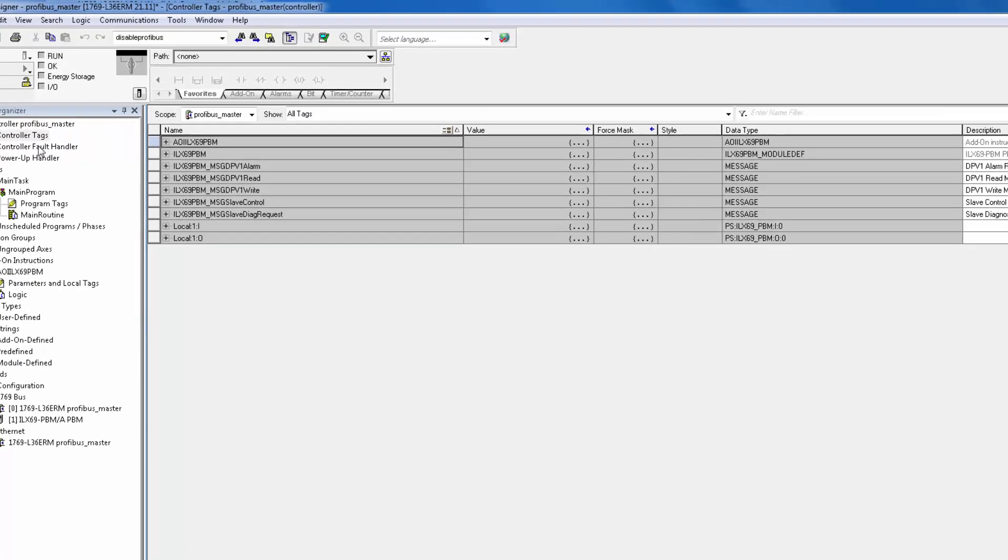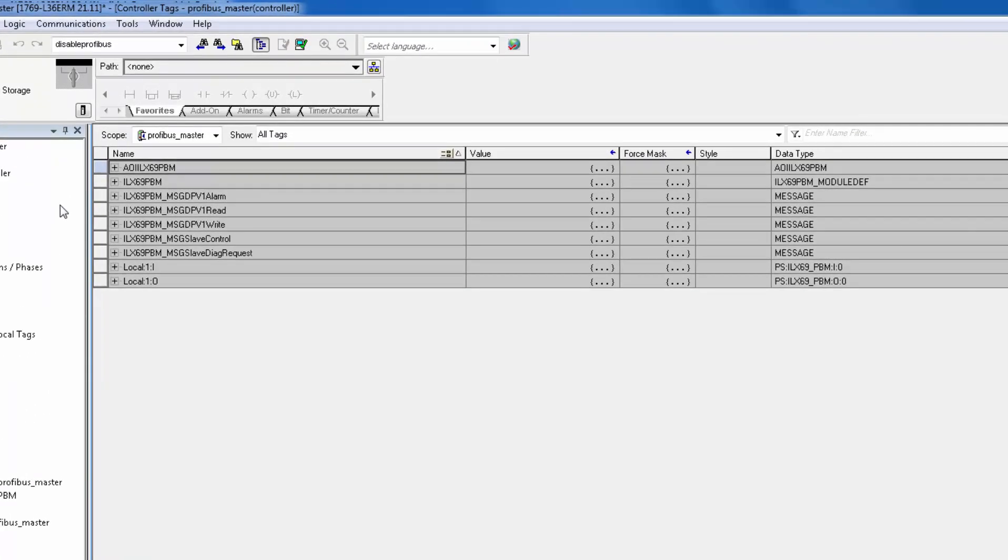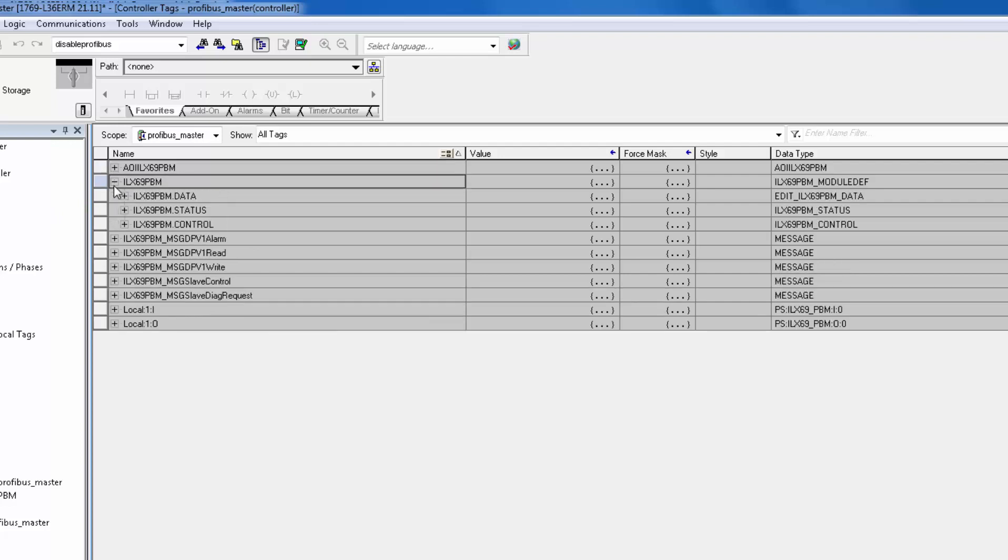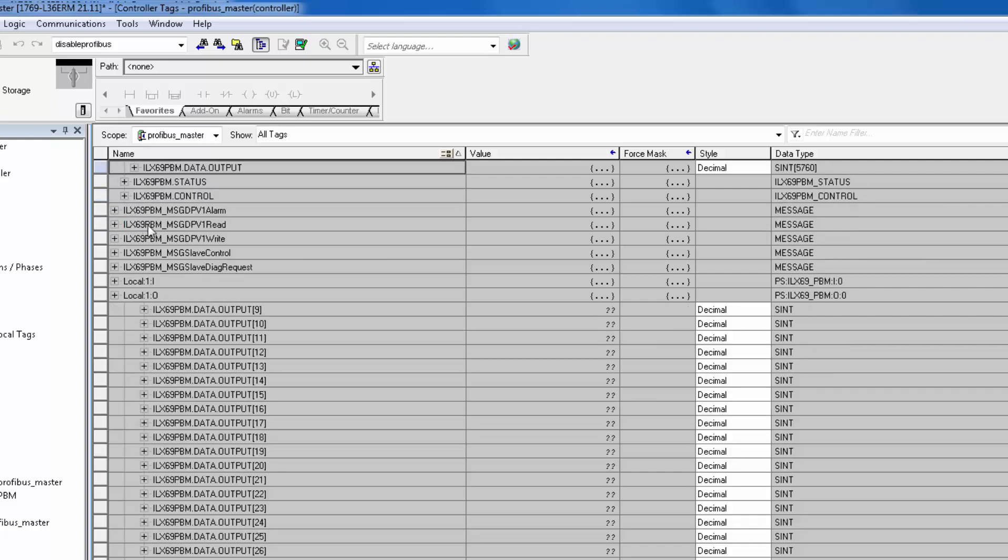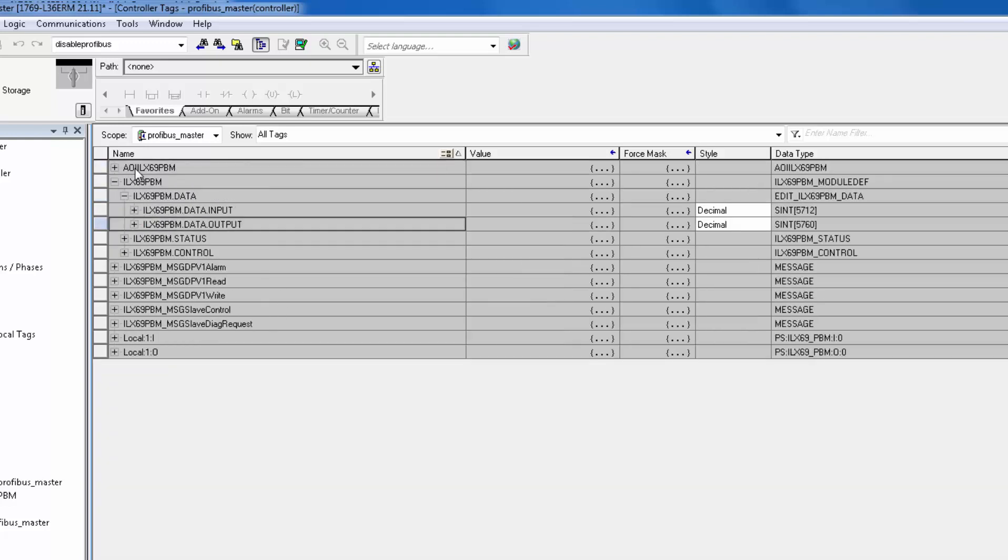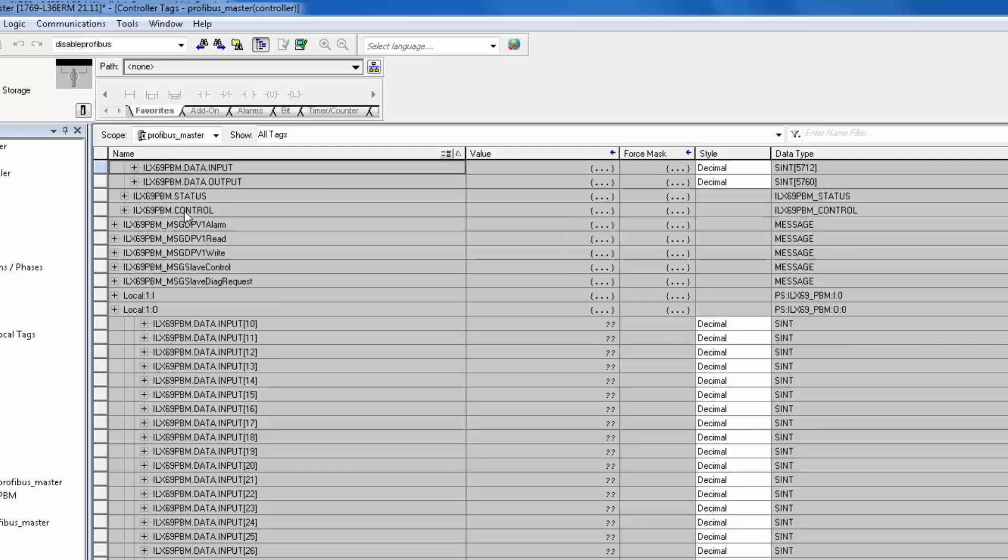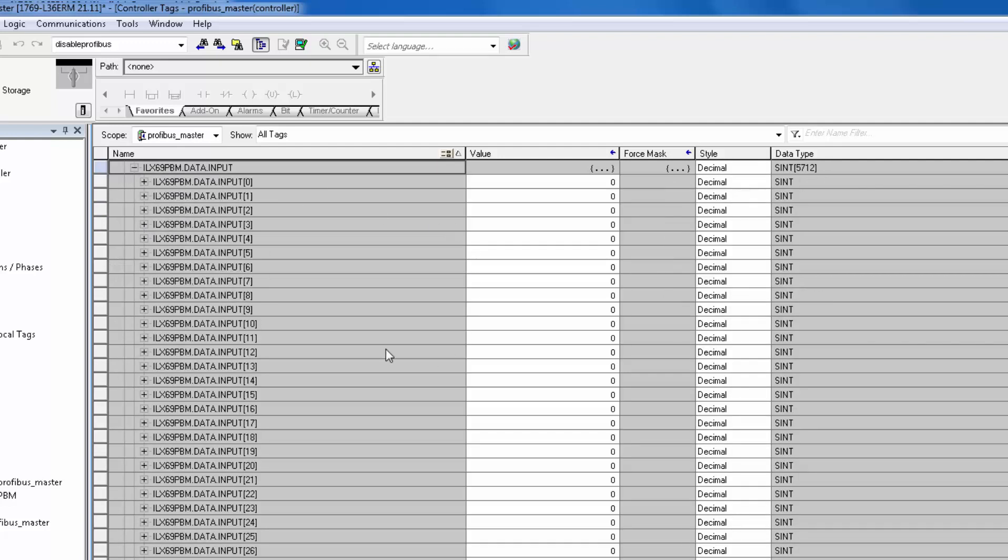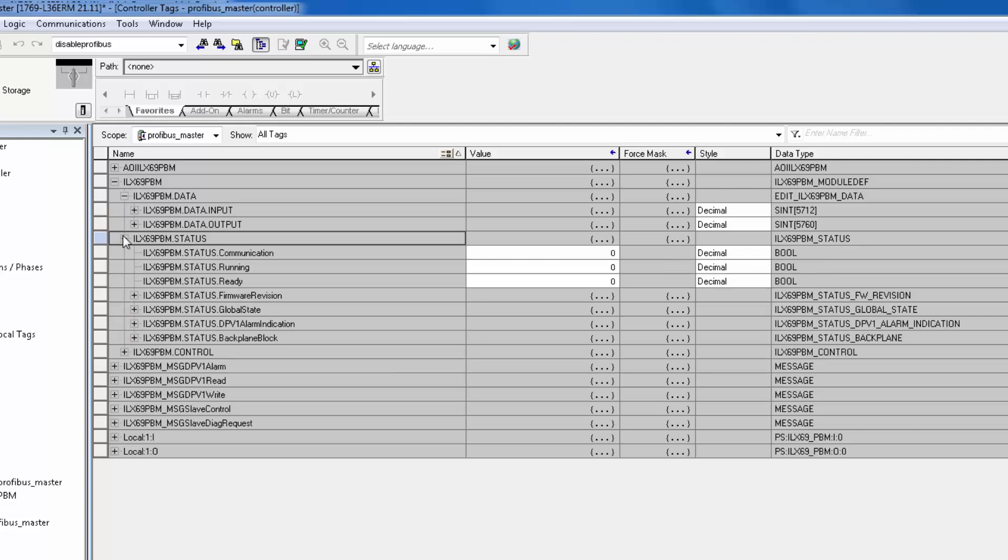Double-click on Controller Tags and expand ILX69 PBM Data, then Output. This array is where we send data to the slaves on the PROFIBUS network. If you expand Input, this is where the master will store the read data from the slaves. Below, in the Status section, is where we can see those diagnostics I was talking about.